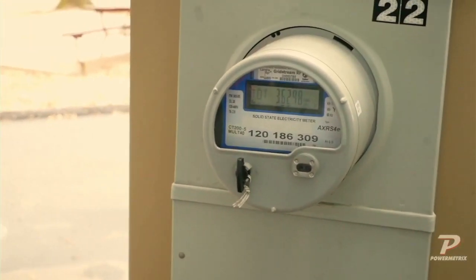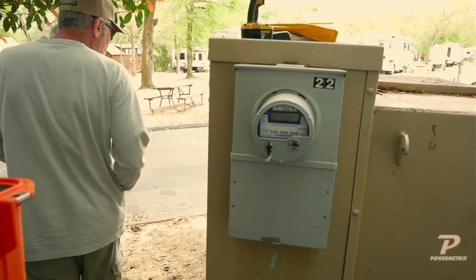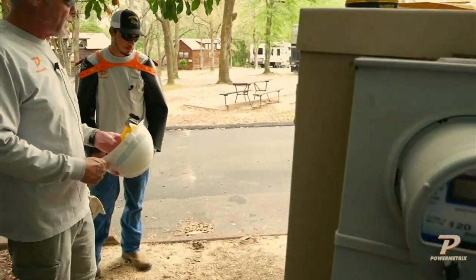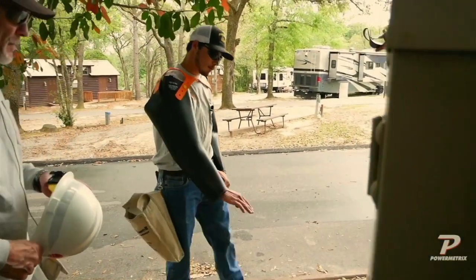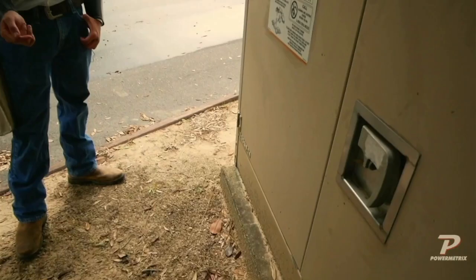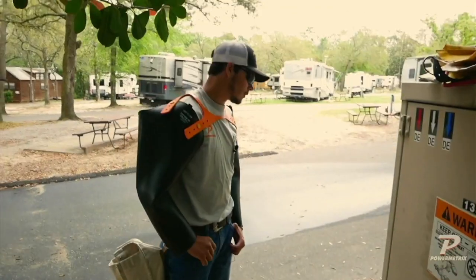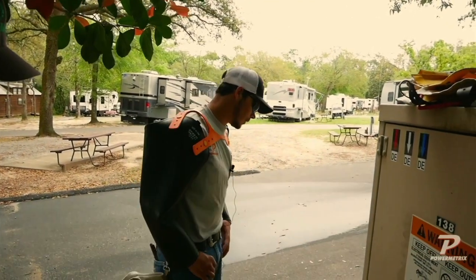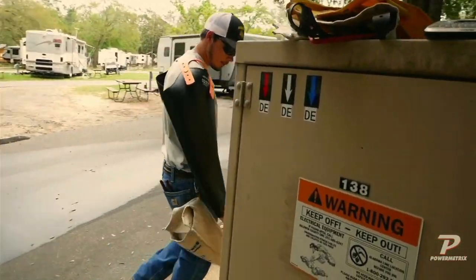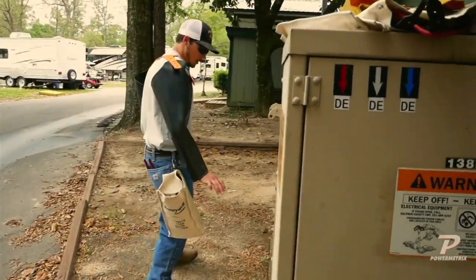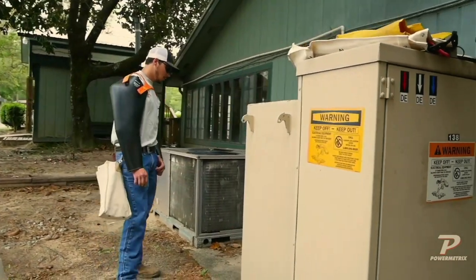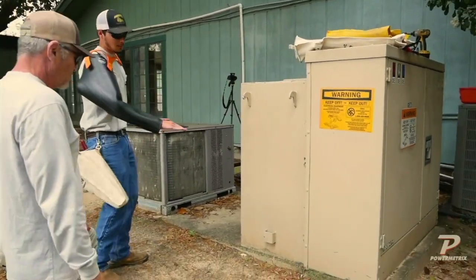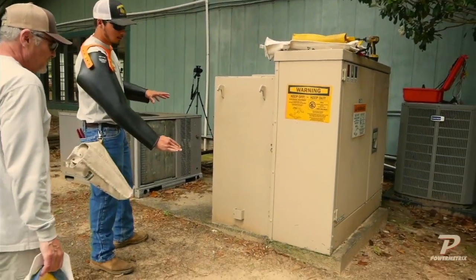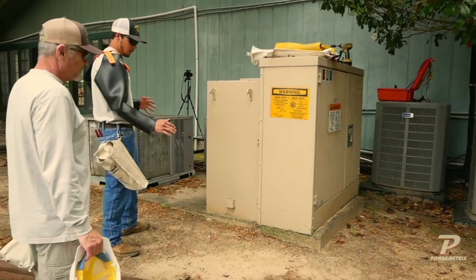So Brian, now let's go ahead and start our inspection. When you inspect a pad mount versus, say, the overheads, what are you looking for here, Brian? You can come over here, look around it, look for oil coming out. You can also smell the oil - it's got a very distinct smell to it. You can just look around, make sure there's no gaps in the transformer or anything like that, and make sure the ground's not settled, where that transformer sunk down in the ground.